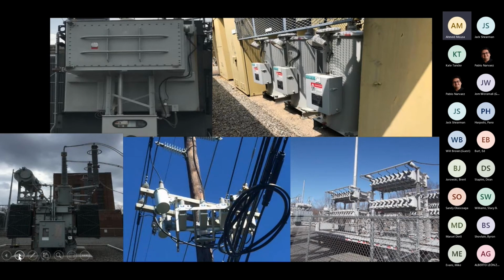We have the tap changer, which is a great tool. One minor issue: the transformer is very expensive. I've seen in my career a transformer fail because the LTC failed. There was a spark that put a hole through the transformer, and it cost a couple million dollars to restore everything because of excessive movement in the tap changer. Again, it's a three-phase system, so if you have 5 or 10 circuits connected, all of them would be impacted.